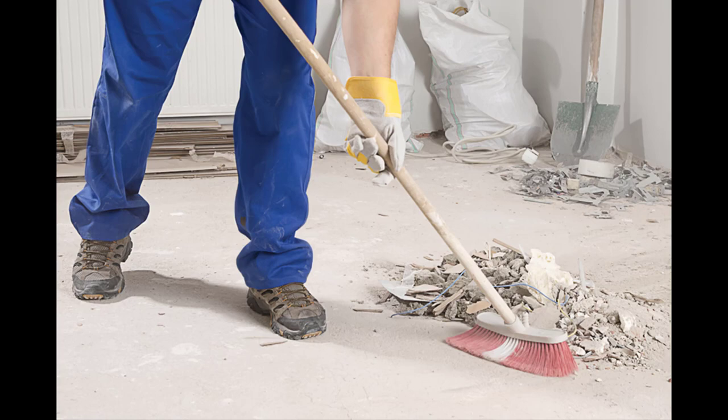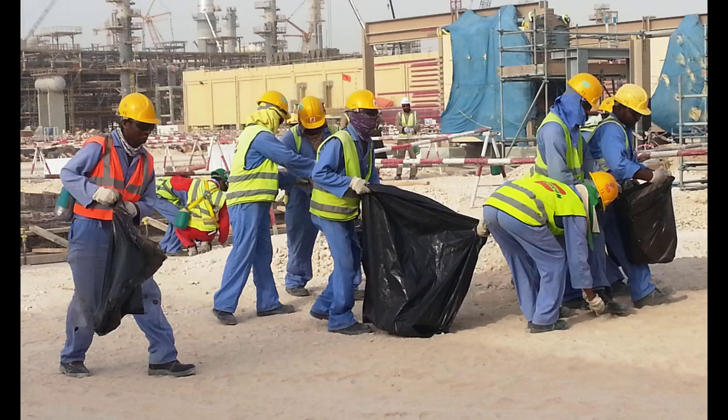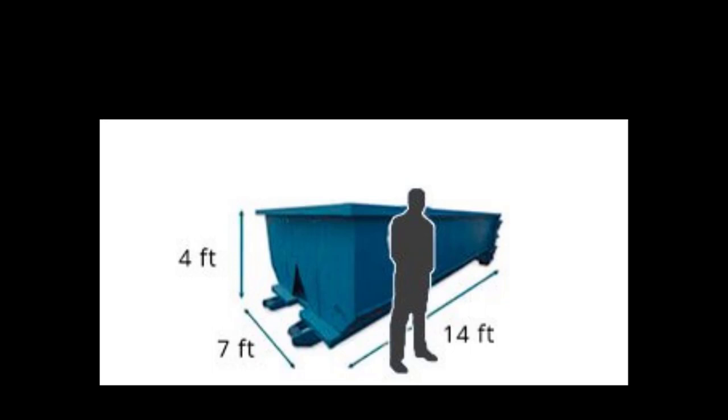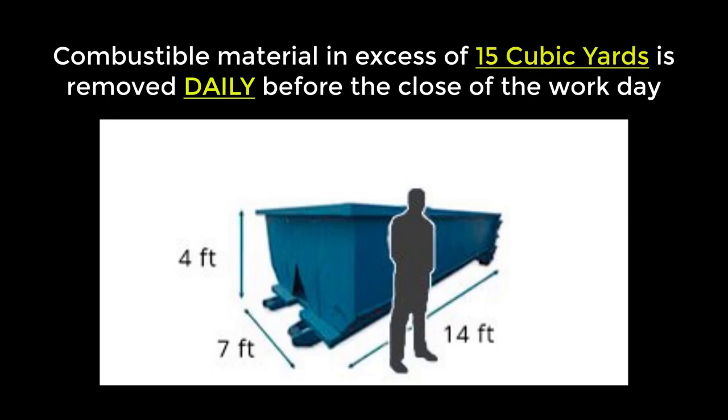Combustible material in excess of 15 cubic yards is to be removed on a daily basis before the close of the day's work. Combustible waste, including rubbish and construction materials, should not be allowed to accumulate on the site.